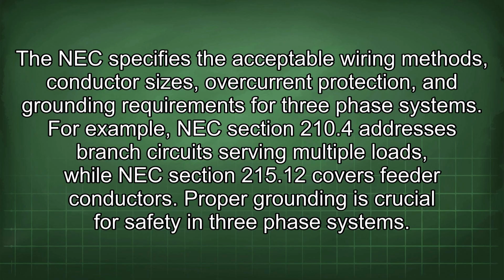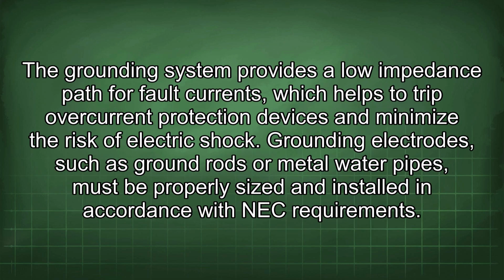Proper grounding is crucial for safety in three-phase systems. The grounding system provides a lower impedance path for fault currents, which helps to trip overcurrent protection devices and minimize the risk of electric shock.